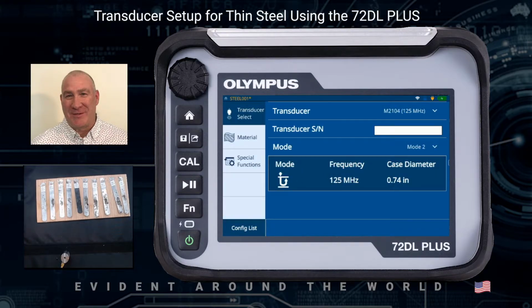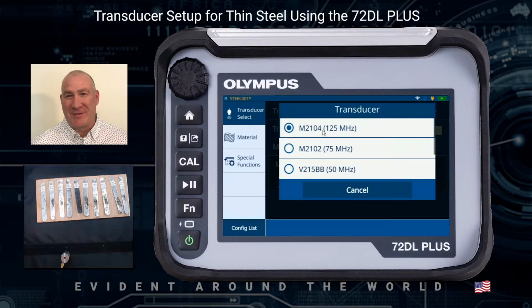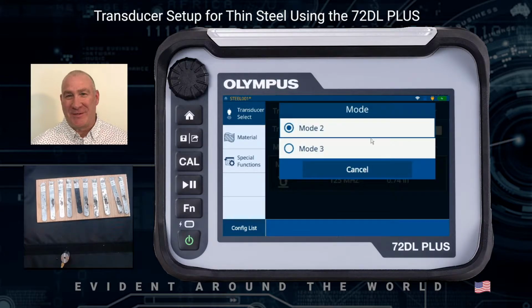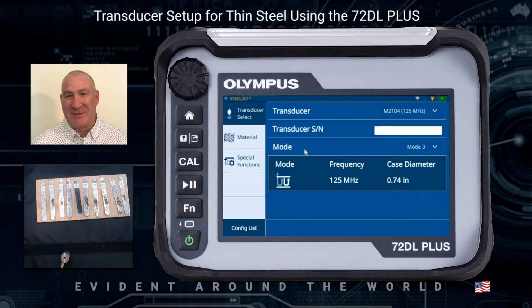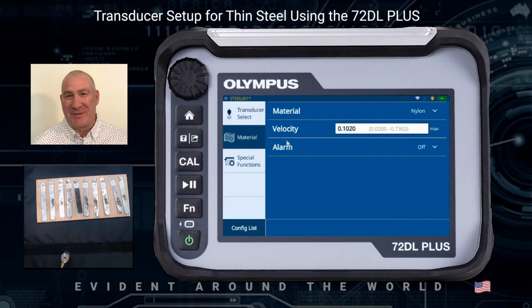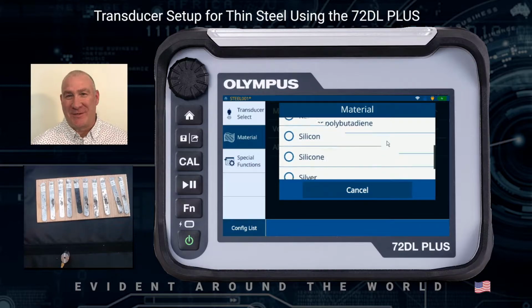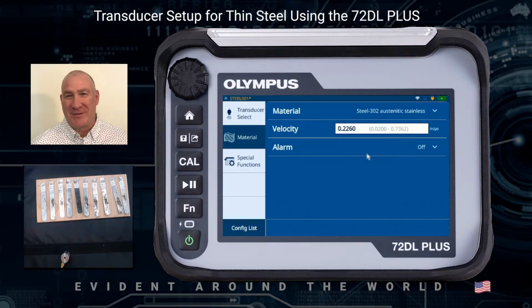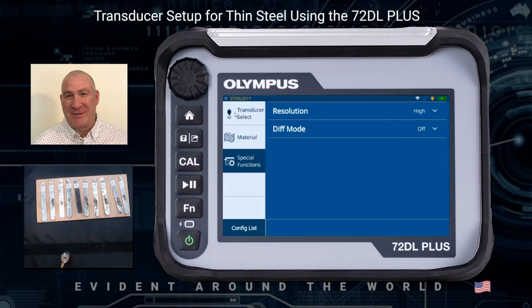This brings me up to my transducer setup and selection screen. First thing I want to do is select the correct transducer. I'm going to be using the 2104 125 megahertz transducer. Select that. I'm going to be doing a mode 3 measurement, so after the surface echo, I'm going to be looking at multiple backwall echoes. Select that, and then I need to go to my material tab and select the material that I'm going to be using. In this case, I want to be using steel. If I scroll down the list, I can get to stainless steel. I can also look at my special functions here. I just want to make sure I'm in high resolution. At this point, I can press the home key, which is right under the knob, to return to a measurement screen.